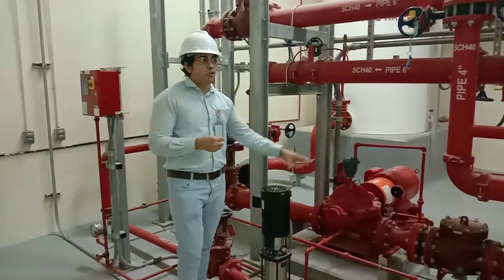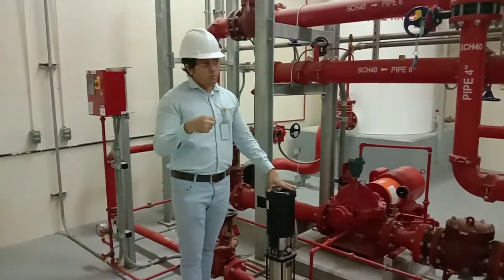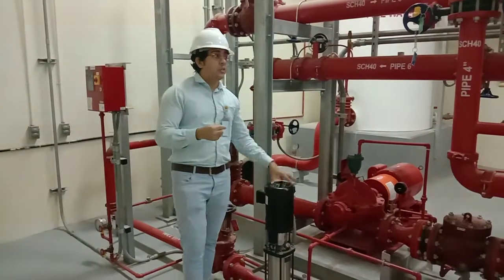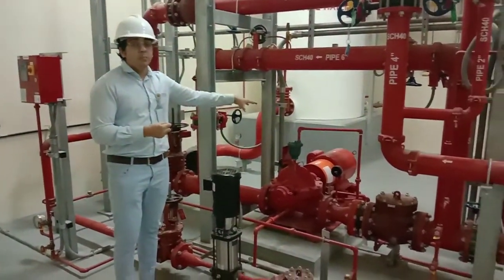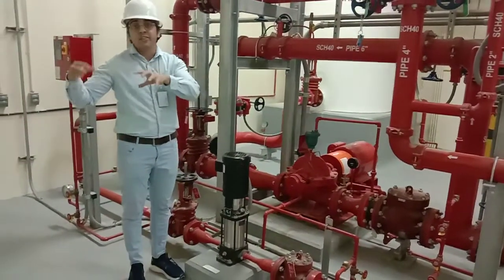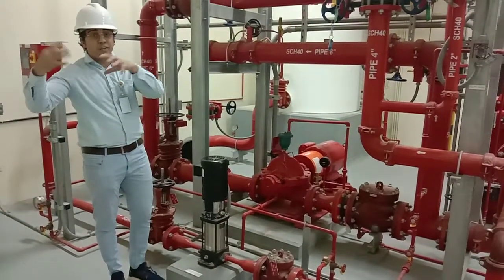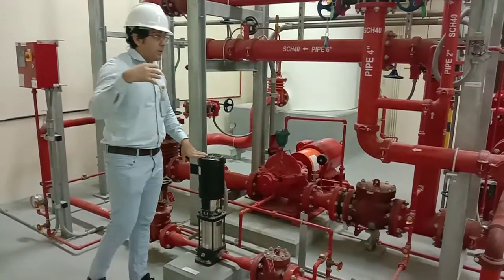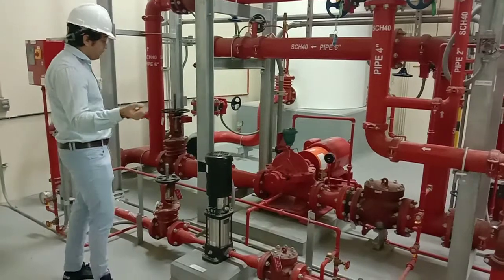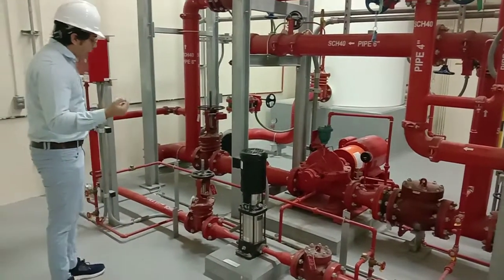We might maintain those pressures by another pump also, because we just want to save the life of the pump, while the main pump is saving the life of the property and the persons inside the healthcare occupancies, and providing protection for the warehouses and the storage areas. This is how it works for the jockey pump.